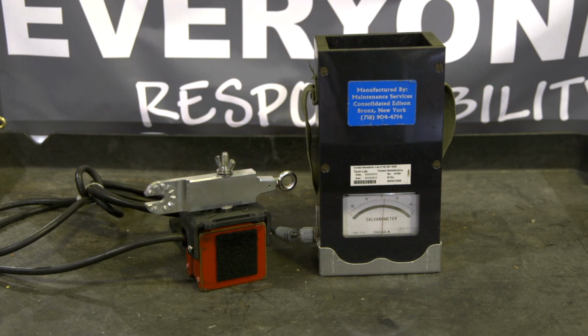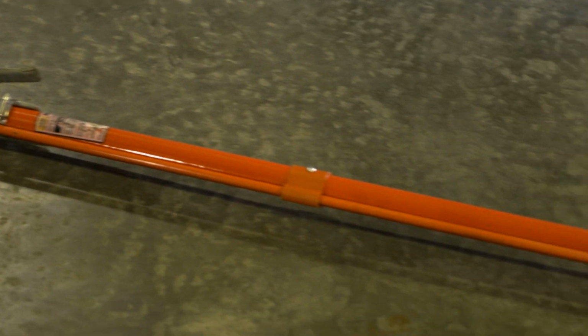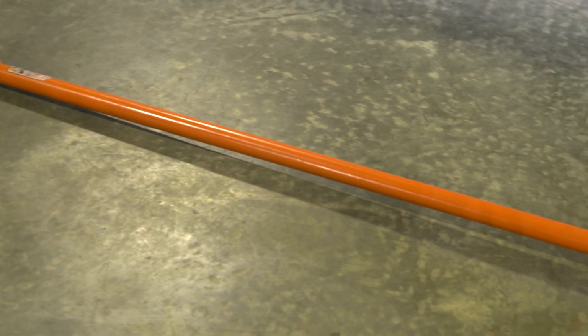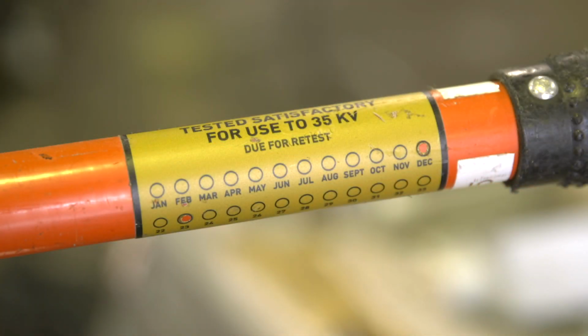Now let's take a look at the galvanometer that you will be using for this job function. Your station should have already been provided with a dedicated galvanometer to verify high voltage tracing current. As you can see, the dedicated galvanometer is fitted with a universal attachment. This will allow you to attach the dedicated galvanometer to both shotgun or test sticks. Whether you're using a shotgun or test stick to perform this job function, make sure you check the stick's expiration date.